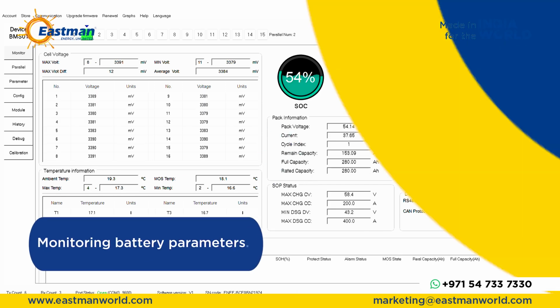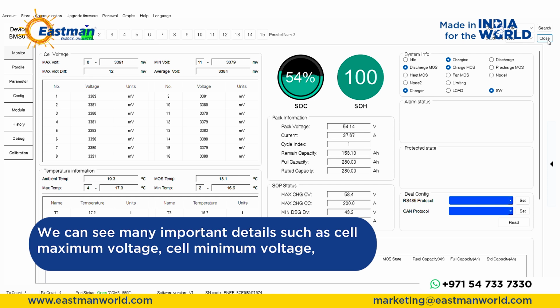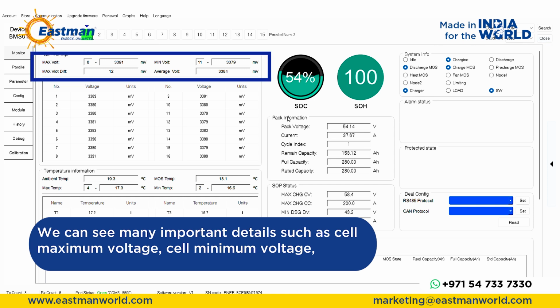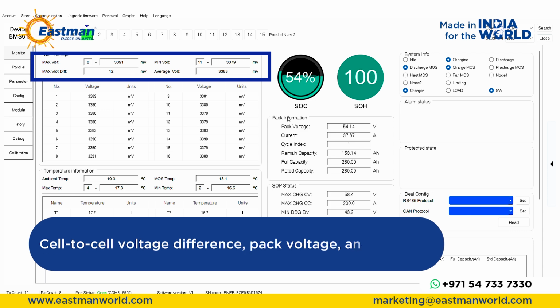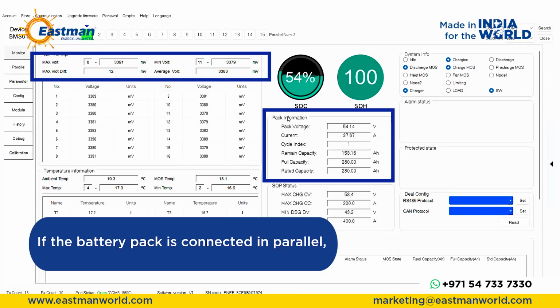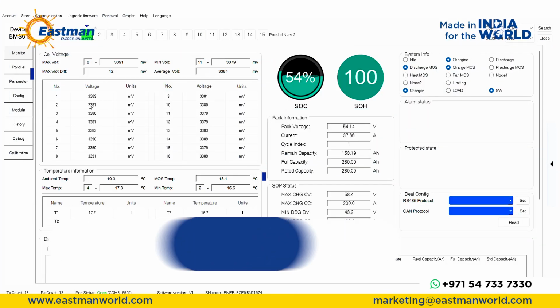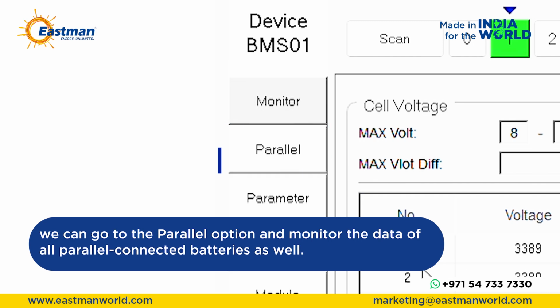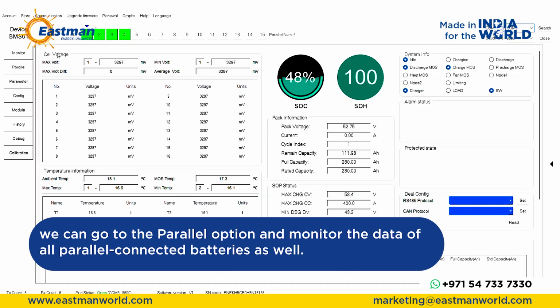Monitoring battery parameters. We can see many important details such as cell maximum voltage, cell minimum voltage, cell to cell voltage difference, pack voltage, current. If the battery pack is connected in parallel, we can go to the parallel option and monitor the data of all parallel connected batteries as well.